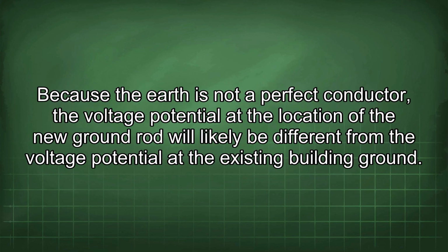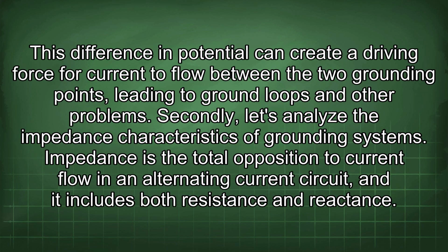Because the earth is not a perfect conductor, the voltage potential at the location of the new ground rod will likely be different from the voltage potential at the existing building ground. This difference in potential can create a driving force for current to flow between the two grounding points, leading to ground loops and other problems.